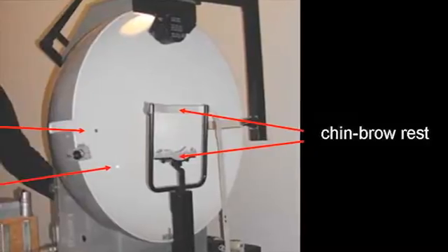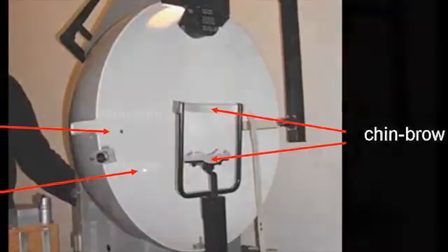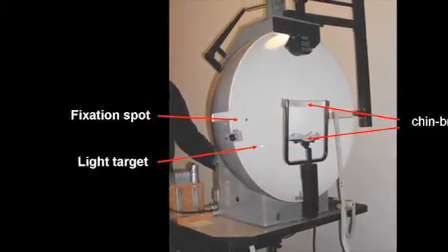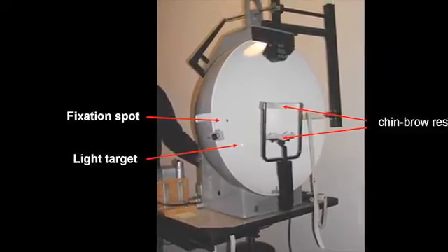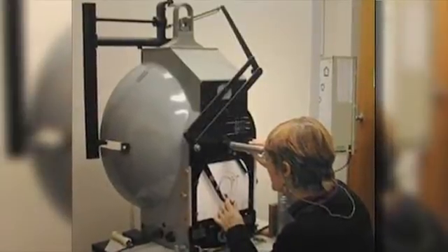In a photograph, we see a hemispheric perimeter. Red arrows point to a chin and brow rest, which allow the head to remain in a steady position during testing, aiding focus on a fixation point at the center of the hemisphere. A bright point in the hemisphere is the light target. We also see the device from the back, with an examiner peering through a scope. Using a Goldmann perimeter chart, the examiner picks a point at which the light target will be presented, and the results are then plotted by the examiner.